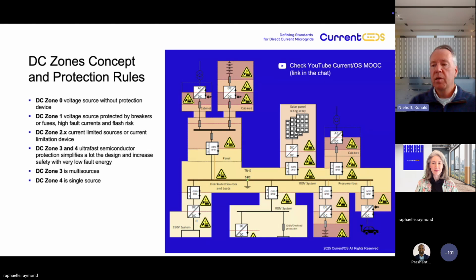Safety zones are extremely important for us. And why? Because it gives you all the benefit of DC, and that's what we do not do in AC. We do not separate high impedance sources from low impedance sources, high energy areas from low energy areas, and that makes it extremely complex to make such installations in AC. And therefore we have this zone system to have the maximum benefit of DC in active prosumer electrical installations. A little bit on the zoning system, however, in the MOOC it is much better explained than I can explain it.